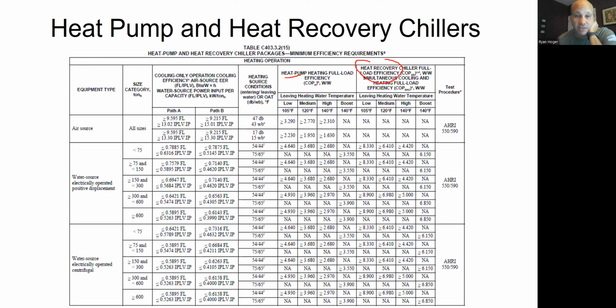So you've got that, and then you have to define the conditions. So if it's an air source one, which we're talking about, you have to meet 2 efficiency levels. You have to meet this efficiency on a 47-degree day, and you've got to meet this efficiency on a 17-degree day. 47 and 17 are the 2 testing points that pretty much all heat pumps use for outdoor air temperature. That's why they're using it again in this table. You have to meet both of those. So over here on the cooling side, you've got to meet one or the other. On the heating side, you've got to meet both of these things. This is all designed to make it very confusing for you. Then you've got to decide what leaving water temperature you have.